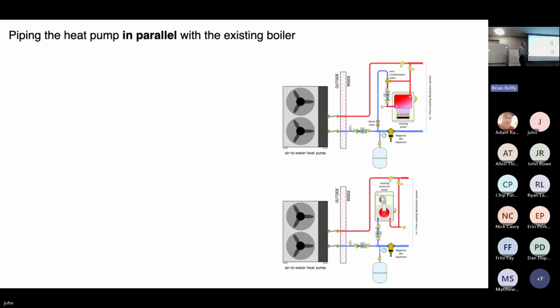What determines when they operate together? It could be a number of things. It could be that the heat pump doesn't have enough capacity if it's extremely cold out. Many of the heat pumps have that control logic built right in. They can fire the boiler when necessary. If you're using what we call a conventional boiler, that would be cast iron, steel, or copper tube boiler. The term conventional boiler means a boiler that is not intended to operate with sustained flue gas condensation.